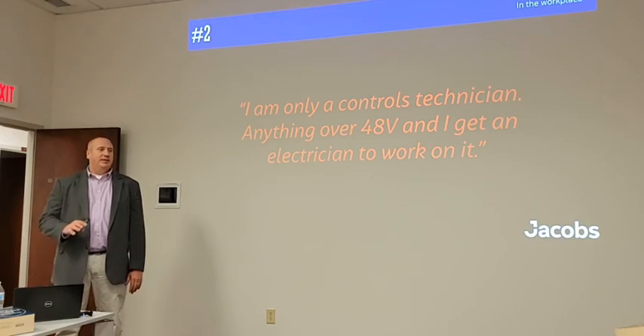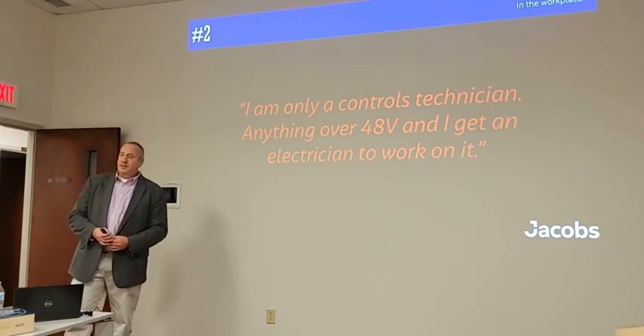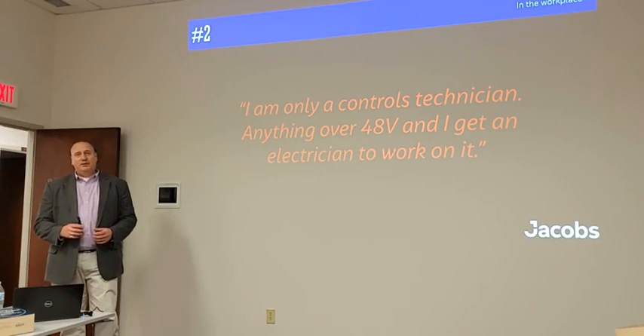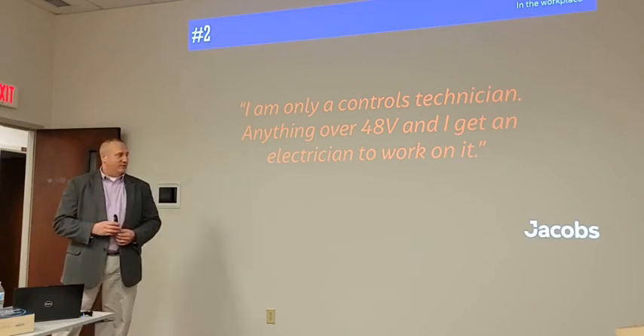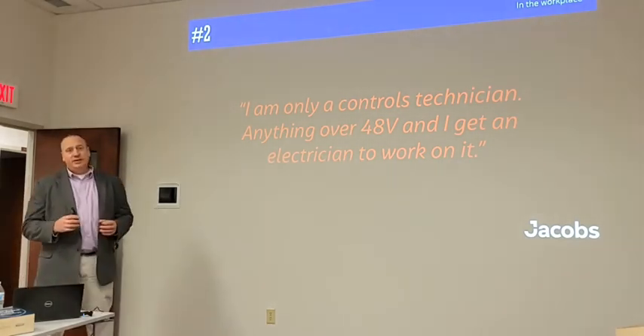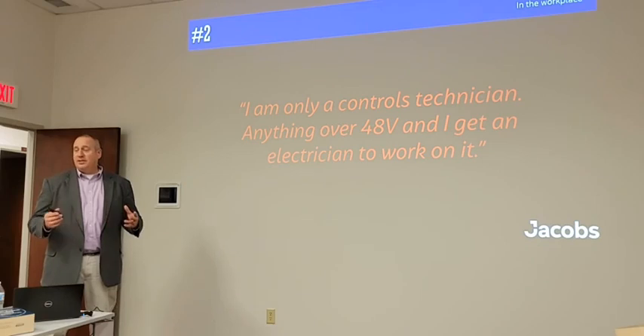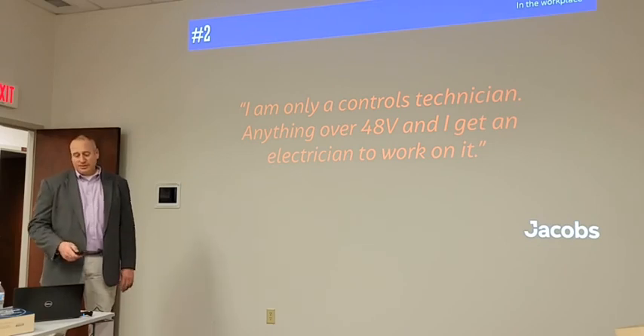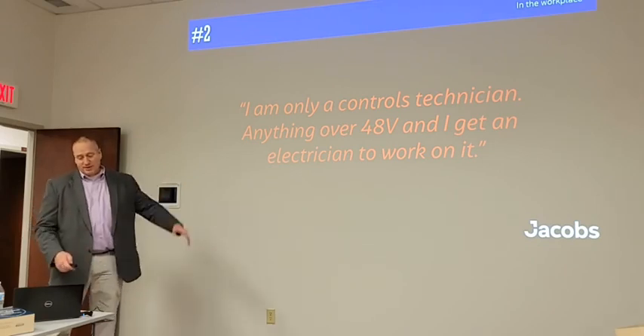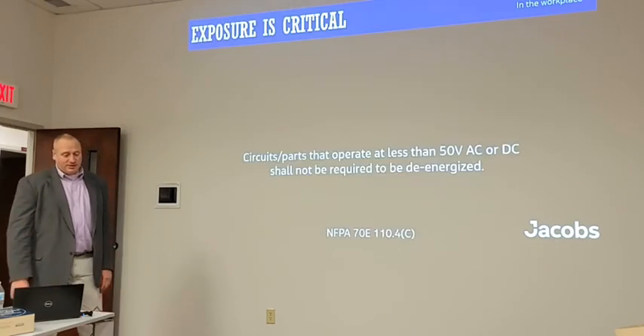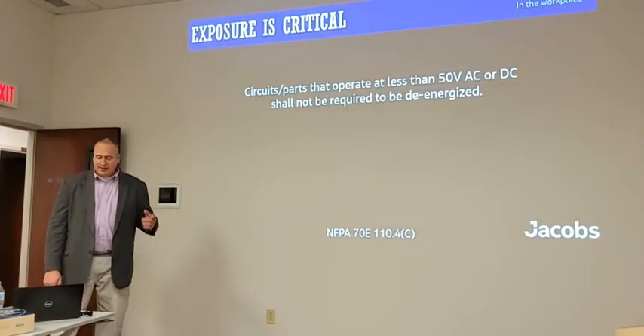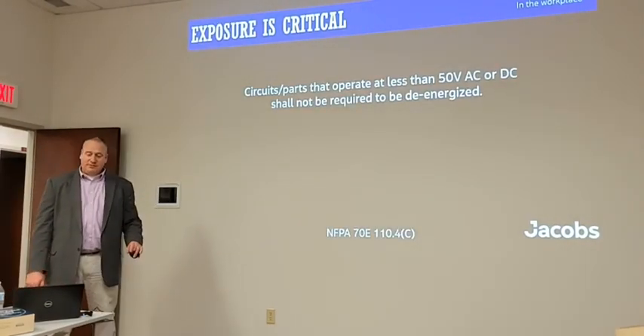There's nobody that knows every single aspect about electrical safety. And so one of the most important things as electrical workers is for us to recognize and admit to ourselves our limitations with electrical equipment. So knowing not to mess with anything over 48 volts is a good start. And what the 70E says is that circuit parts that operate less than 50 volts AC or DC shall not be required to be de-energized.